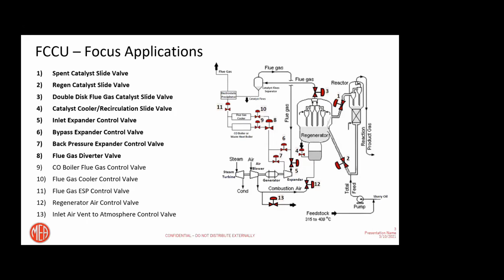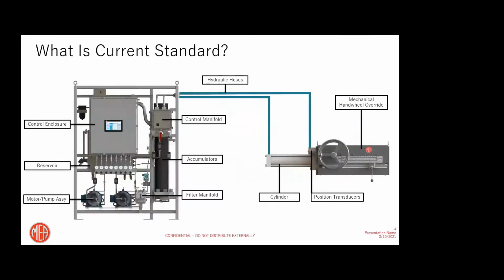So these valves are required to provide extreme accuracy of positioning and very high speed. Additionally, they require the ESD, really high speed ESD. And further, of course, these valves are required to be really fast. So all of these requirements leave only one choice for these valves: electrohydraulic actuators.